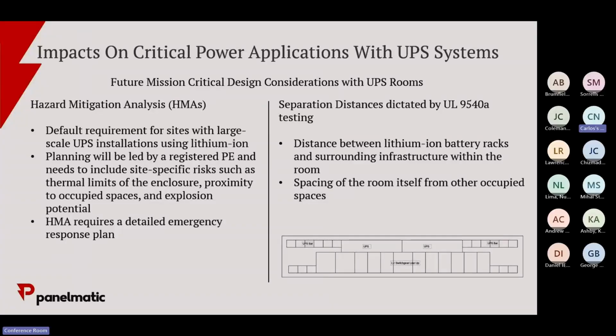On a UPS system like this, instead of having to open those doors, the thought is if you can basically have an inlet and an exhaust fan, you can move enough airflow without having to open all the doors. The energy density on those is much less than say a large BESS where you're talking 2 megawatts power and 4 megawatts energy. These are probably much less than that.